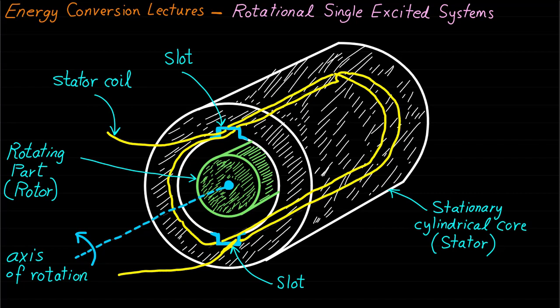The shape of the rotor is cylindrical, and that is why we call it a cylindrical rotor. Both stator and rotor are made from magnetic materials. The air gap between the stator and rotor is to allow for the rotation of the rotor. Note that the air gap in real machines must be very small to increase the magnetic field density of the machine, so the large air gap in this figure is just for explanation purposes only.